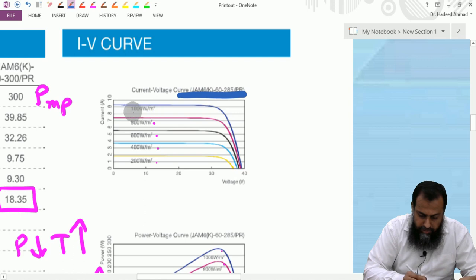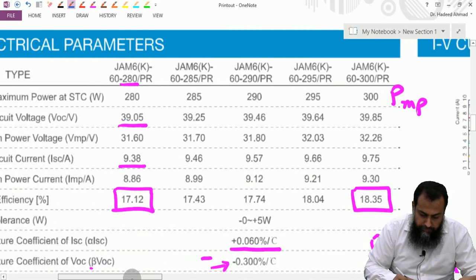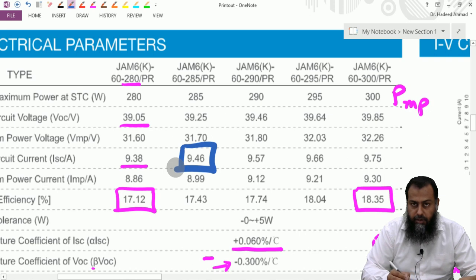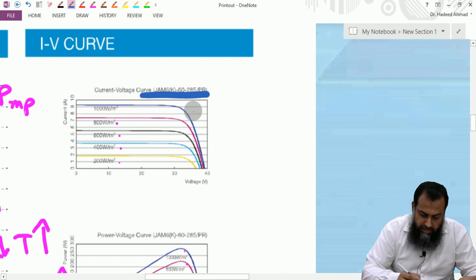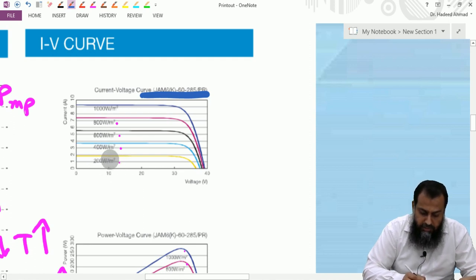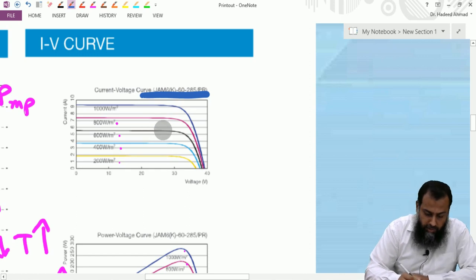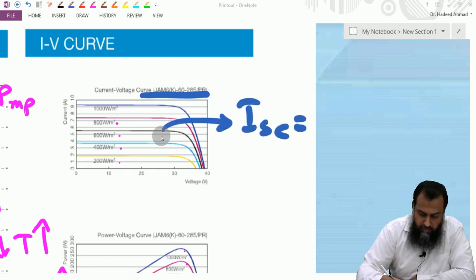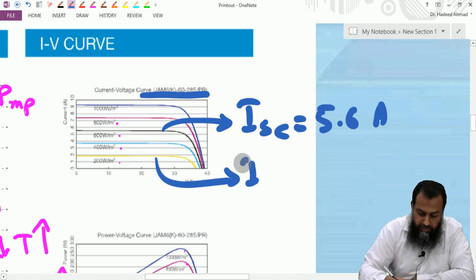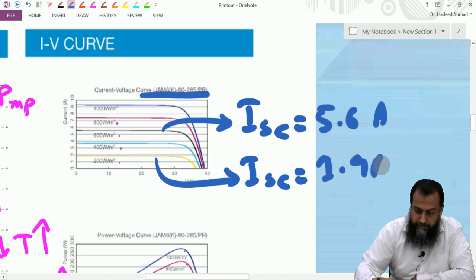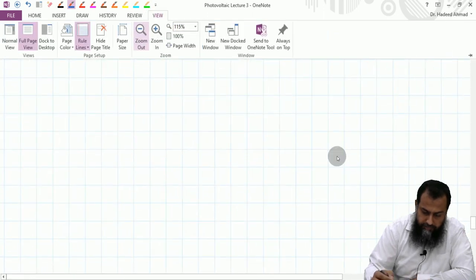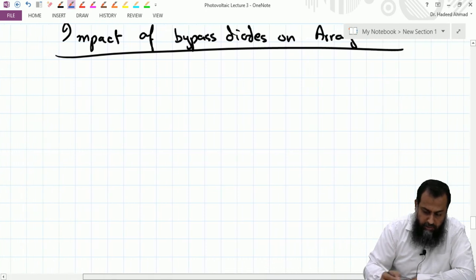At 1000 W/m² irradiance, this module is capable of providing a short circuit current ISC equal to 9.46 ampere. At 600 W/m² irradiance, ISC is around 5.6 ampere, and at 200 W/m² irradiance the same PV panel has ISC equal to approximately 1.9 ampere. Based on these three values we will understand the impact of the bypass diode on the PV array.